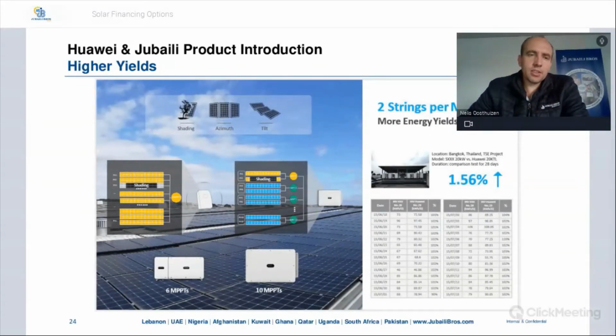So higher yields, how are higher yields possible on Huawei inverters? The Huawei inverters have multiple MPPTs, and you also have 2 strings per MPPT. If we focus specifically on the 100 kTL, which has 10 inputs or 10 MPPTs, and a certain section of your installation is affected by shading, only that one MPPT will be influenced and it will have no influence on the rest.